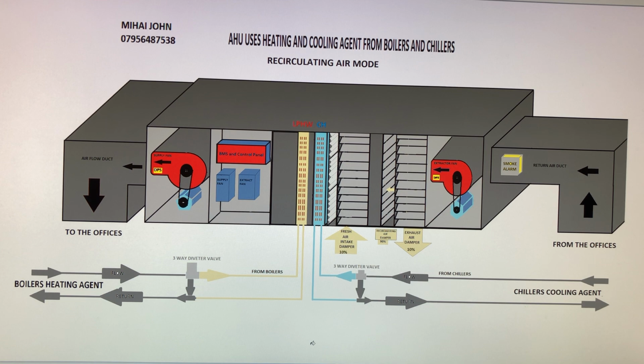But it came to the point where that's not enough. Let's say the temperature in the store starts to rise. It's the middle of the summer. I have 30 degrees outside, and 27 degrees inside the store. The building management control will analyze the outdoor temperature, and it will sense that if I open the intake damper more to take air from outside, it won't do any good because the air outside is 30 degrees. It's hotter than the air in the building, which is 27 degrees. So the only thing I can do is bring in hot, humid air, which will make things worse.